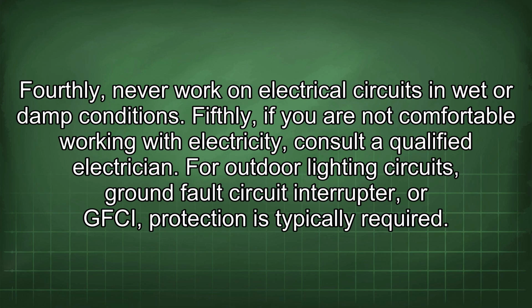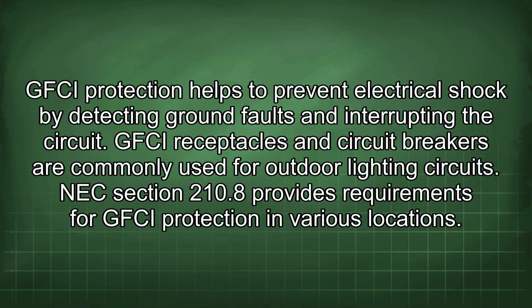For outdoor lighting circuits, ground fault circuit interrupter, or GFCI, protection is typically required. GFCI protection helps to prevent electrical shock by detecting ground faults and interrupting the circuit. GFCI receptacles and circuit breakers are commonly used for outdoor lighting circuits. NEC Section 210.8 provides requirements for GFCI protection in various locations.